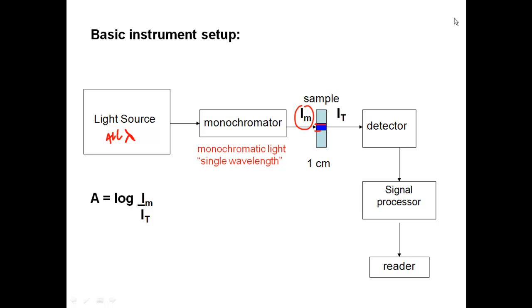Only that cross-section of the sample that the light is going through is absorbing the light — not the entire sample, just that area. Then we measure the intensity of light after. That goes to the detector, the signal is processed, and the reader reads out the absorbance. The absorbance relationship is given by the equation A equals log of I_m divided by I_t, where I_m is the monochromator intensity and I_t is the transmitted intensity.